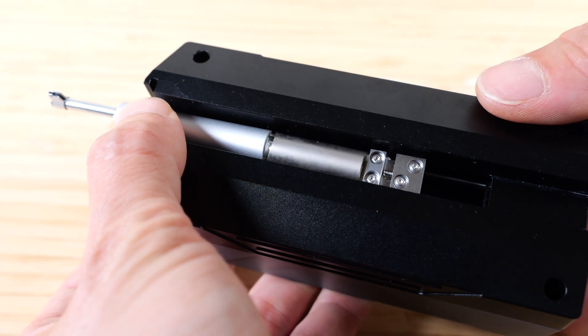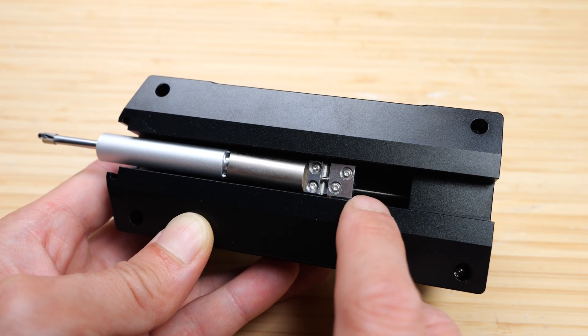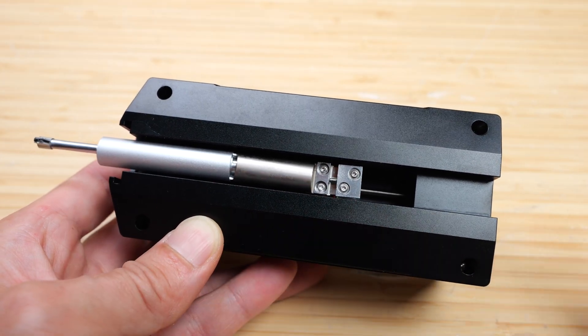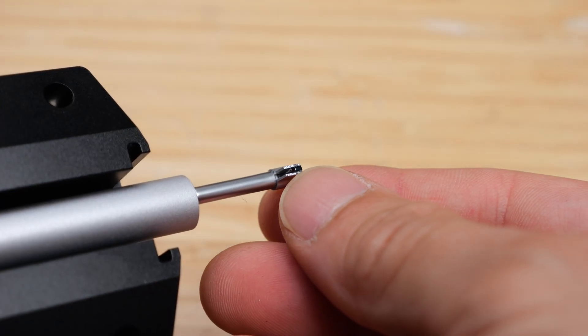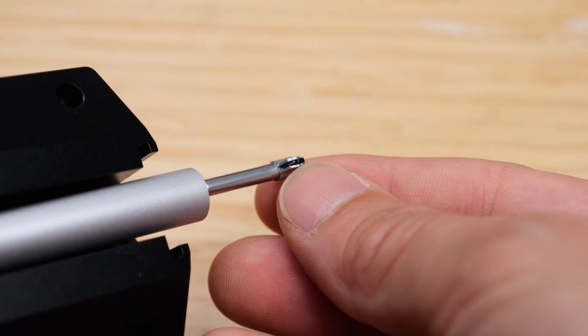I push start and get 2.671. Internally there's a drive screw — you can see it over there — that moves this whole assembly in and out very slowly. You can see right in the center there is a needle-like thing. This needs to be very, very fine in order to get into the grooves.